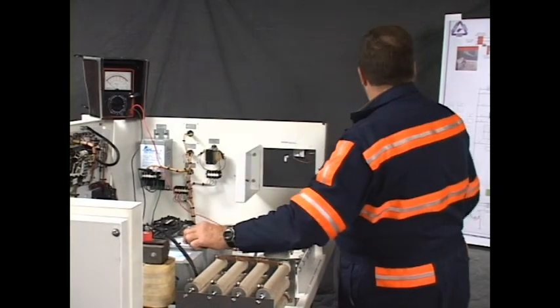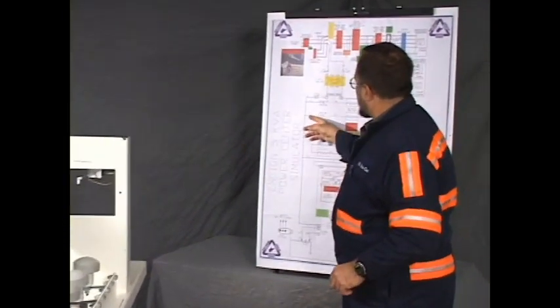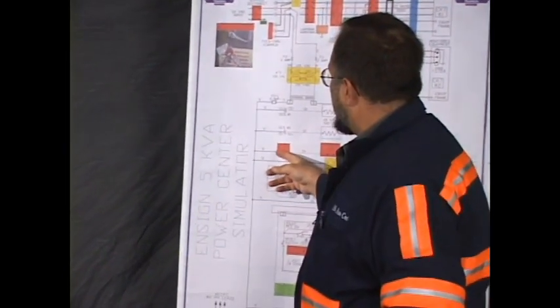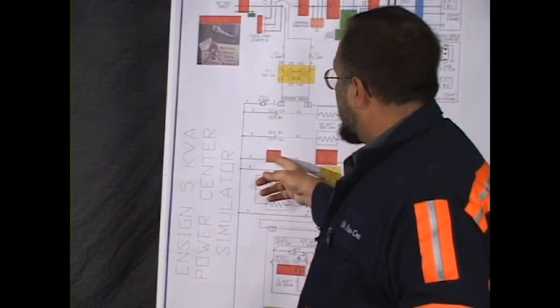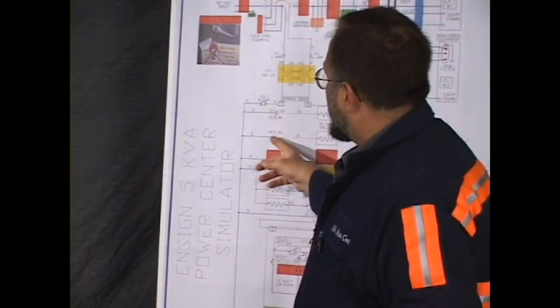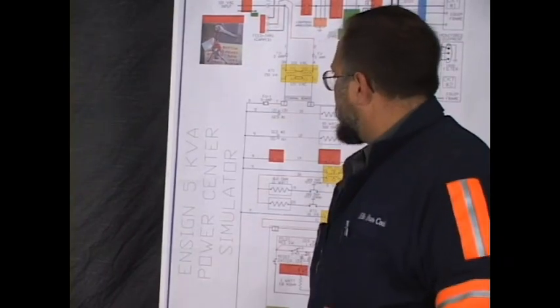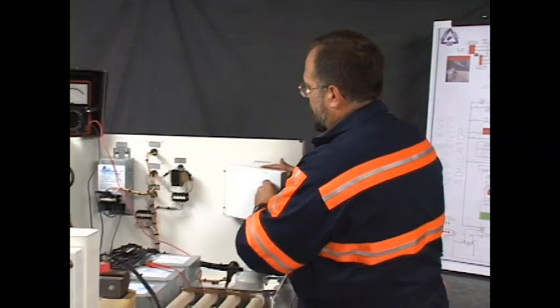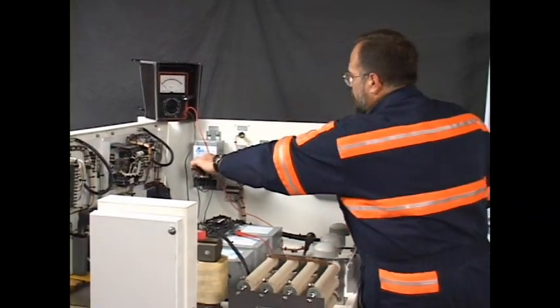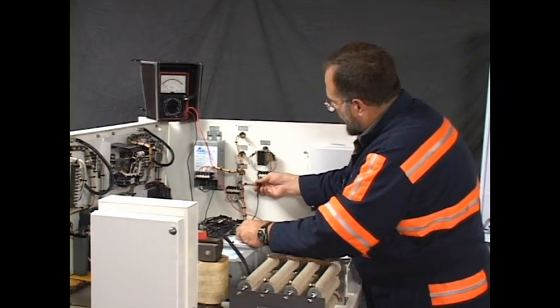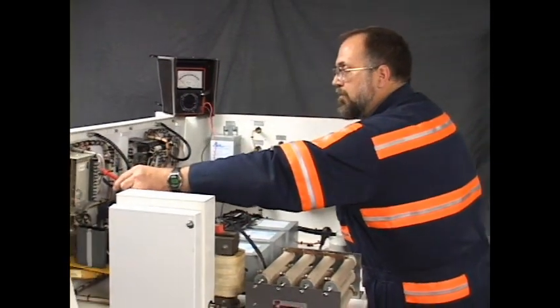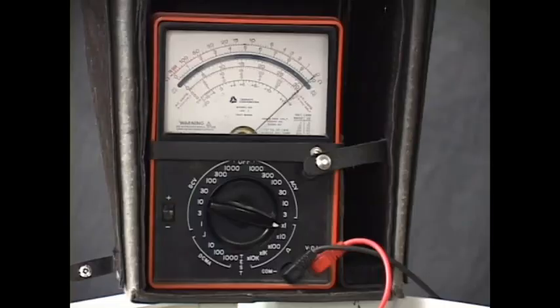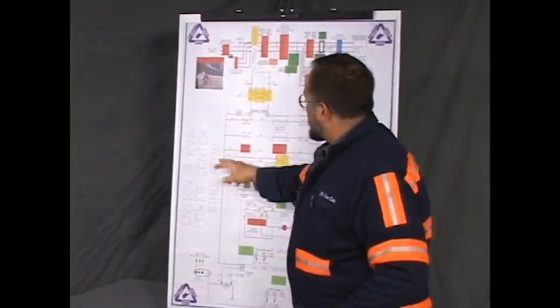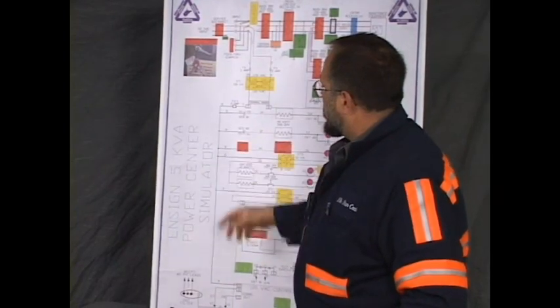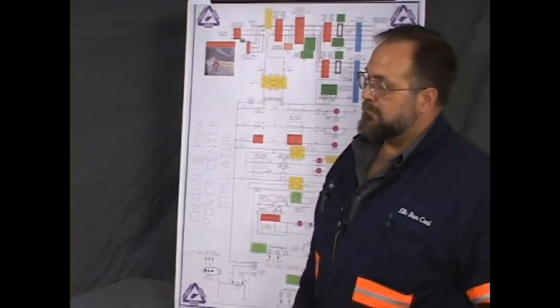So our problem lies between this point here, GCS2, and wire number 9 on the door switch. Now to further pinpoint this, I'm going to read from GCS2 to KT3, the H1 terminal of KT3 for wire number 9. We'll move my black probe and use it on the terminal for KT3 and take my red probe to 9. I've got some continuity there. I have a circuit. That tells me the wire 9 is intact from GCS2 to KT3. It's only open here. That pinpoints the problem. And that's that.